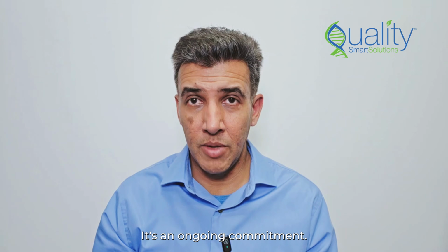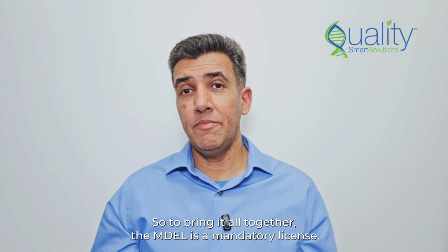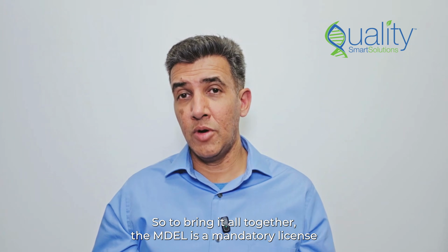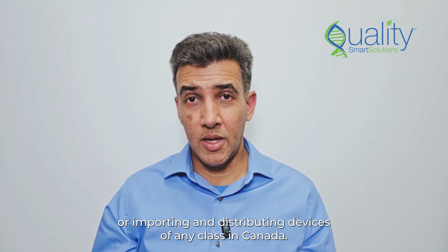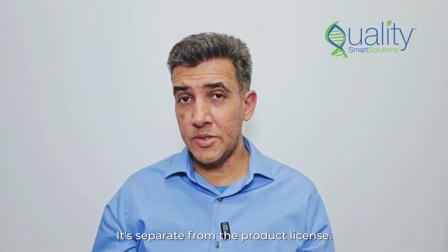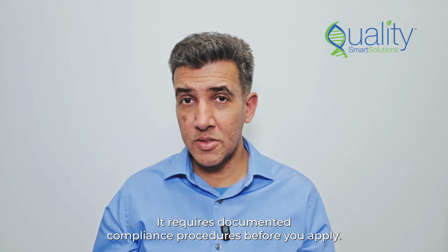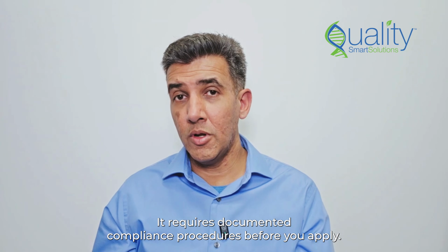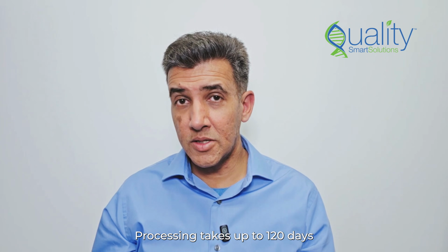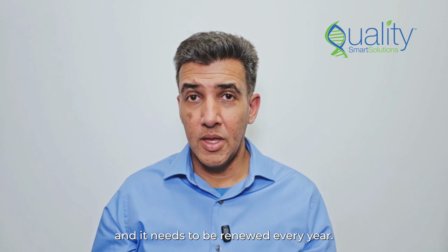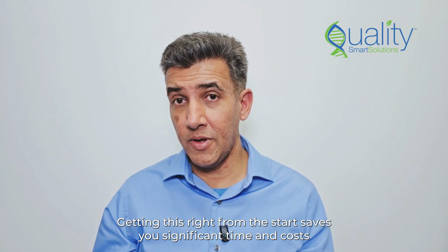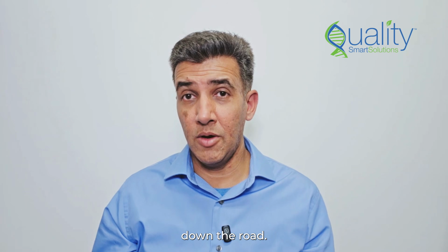It's an ongoing commitment. So to bring it all together, the MDEL is a mandatory license for any business manufacturing Class 1 medical devices or importing and distributing devices of any class in Canada. It's separate from the product license. It requires documented compliance procedures before you apply. Processing takes up to 120 days and it needs to be renewed every year. Getting this right from the start saves you significant time and costs down the road.